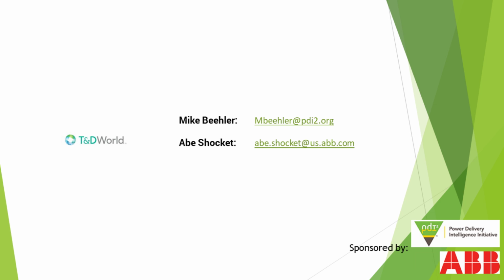I also will say, it's when you have a standard or a utility practice that says, hey, I have to meet 20 kA or whatever you have to meet, and that's the way it's always been, it's difficult to go back and do the studies and confirm what the short circuit current available really is. Sometimes it's not 25 kA. Sometimes it's 20, sometimes it's 16. Sometimes if you're a mile from the substation, it drops off dramatically. So these things can allow you to differentiate which gear selection you make.